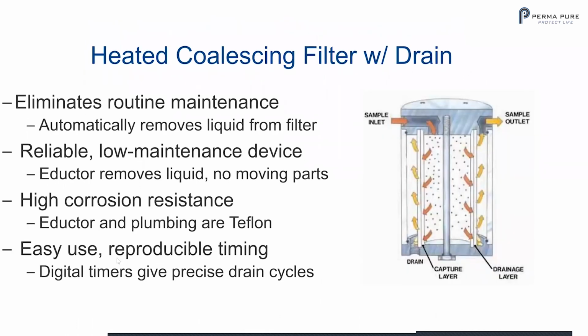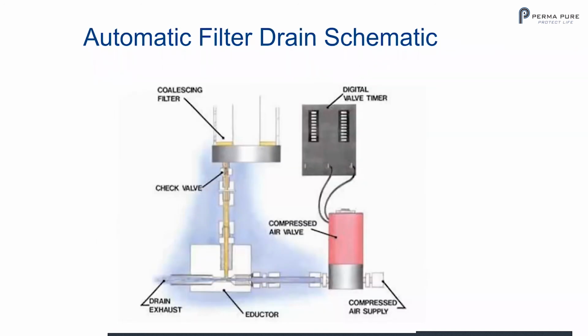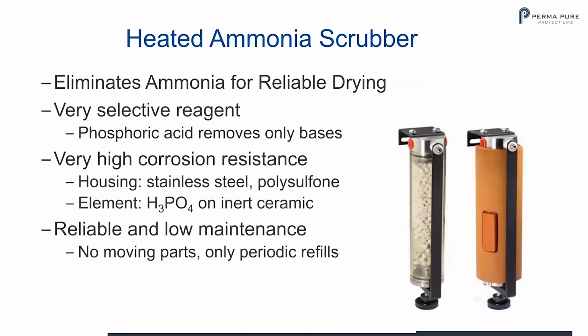Some of the components inside are a heated coalescing filter with drain. This eliminates routine maintenance. It's a reliable, low maintenance device, and it's easy to use with reproducible timing. Here's your automatic filter drain schematic. We also have a heated ammonia scrubber. Here we have a selective reagent: phosphoric acid that is placed on ceramic saddles. That removes the ammonia from the sample stream.